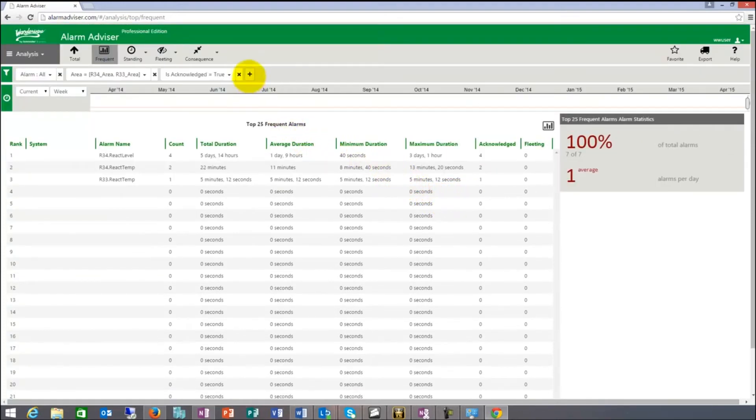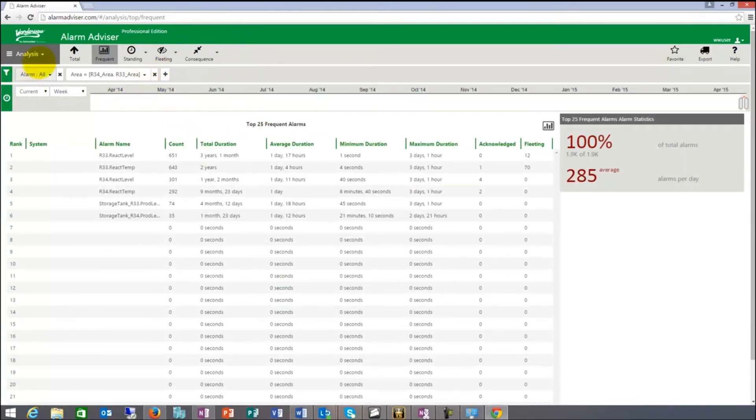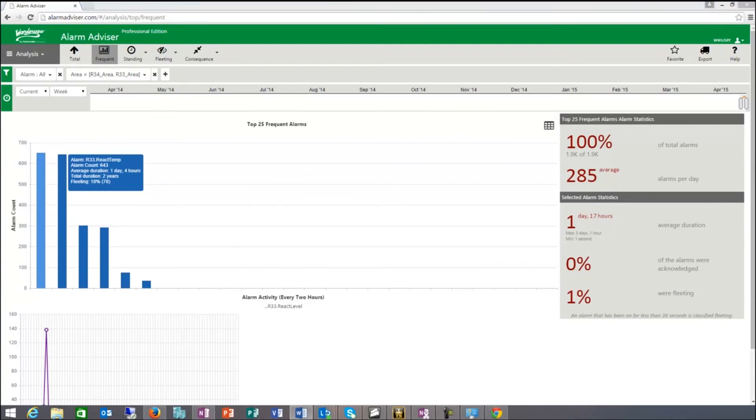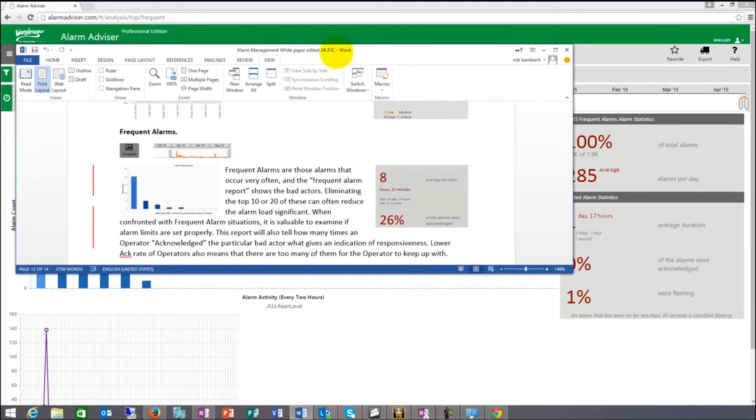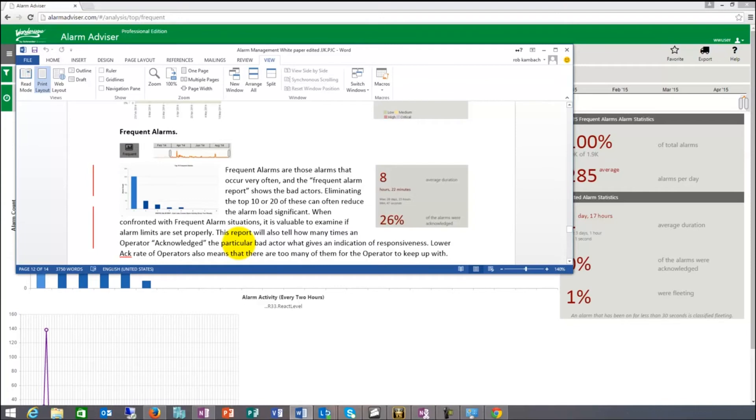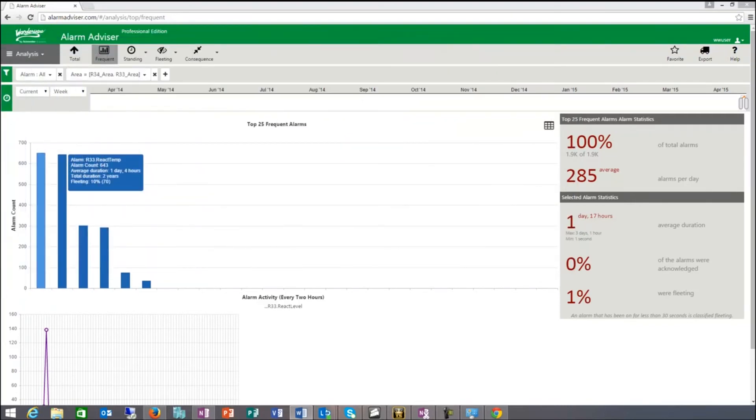Let me show you and bring back that Word document for you for a minute. The frequent alarms are those alarms that occur very often. The frequent alarm report shows the bad actors. Eliminating the top 10 or 20 of these can often reduce the alarm load significantly. When confronted with frequent alarm situations, it's valuable to examine if the alarm limits are set properly in this case. This report will also tell how many times an operator acknowledged the particular bad actor, which gives an indication of responsiveness. And not only that, lower Ack rate could also indicate that operators have too many alarms and basically are unable to keep up with.